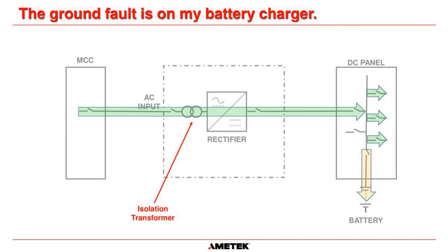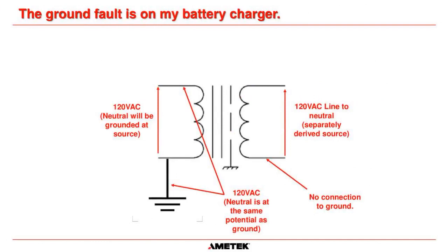But most people think that because the alarm is on the charger, you usually have an alarm signal on your charger that says DC ground fault. They think because they see that on the charger, then the ground fault is within the charger itself. And that usually is not the case, okay? Because we have an isolation transformer in all of our industrial UPSs, okay? And in most circumstances, in fact, it's usually down to electrical code, the neutral of the input to the system will be connected to ground.